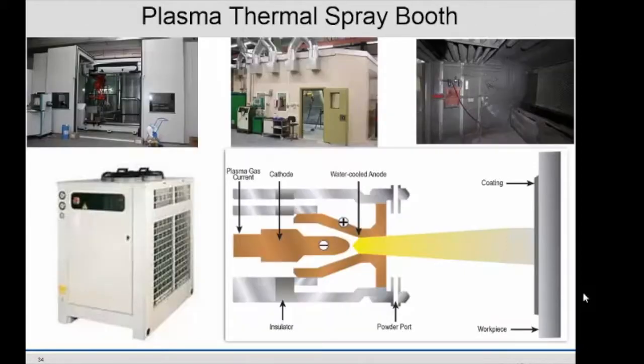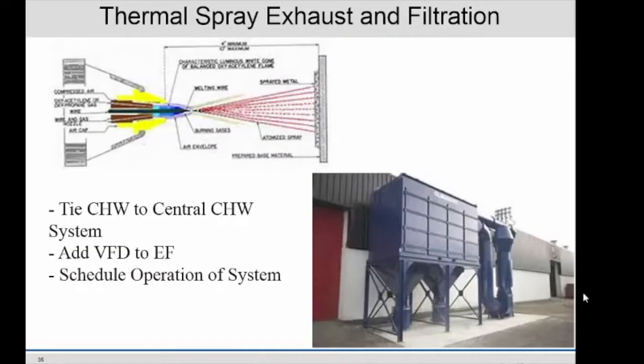How am I doing on time? 5 minutes. Okay, thermal spray booths. These are pretty complex, and they spray kind of a molten ceramic or some kind of a high wear surface onto these metal parts. They have to be cooled. So they have these air-cooled chillers, which are very inefficient. You know, tie it into your central chill water system that's more efficient. You know, that's one way of saving energy. Then also, you're going to have filters. They filter that air. And so with these filters, you want to put VFDs on the exhaust fans and lower that airflow when they're not doing the thermal spray. They got to keep the room pressurized, but reduce the airflow when you're not doing the thermal spray with VFDs and the controls.